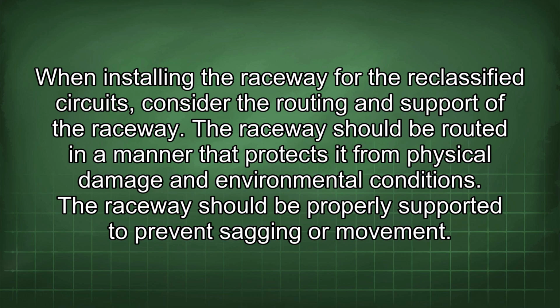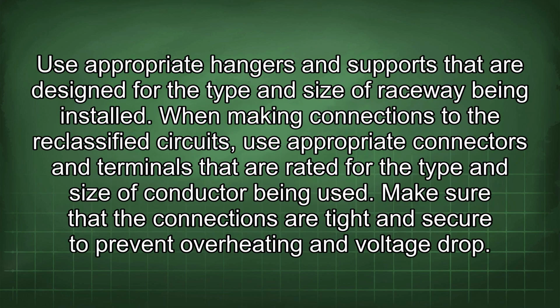When installing the raceway for the reclassified circuits, consider the routing and support of the raceway. The raceway should be routed in a manner that protects it from physical damage and environmental conditions. The raceway should be properly supported to prevent sagging or movement. Use appropriate hangers and supports that are designed for the type and size of raceway being installed.